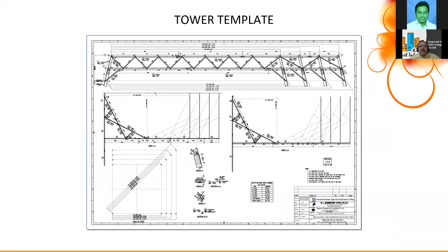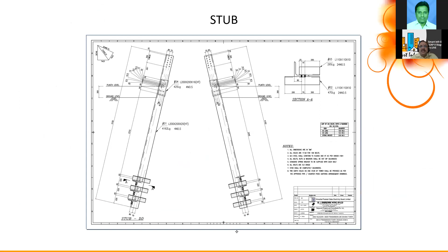Hot curve for clearance and cold curve for tension. This is the stub drawing. You can see these cleats, which we designed as bearing cleats for 50% of the uplift resistance capacity.